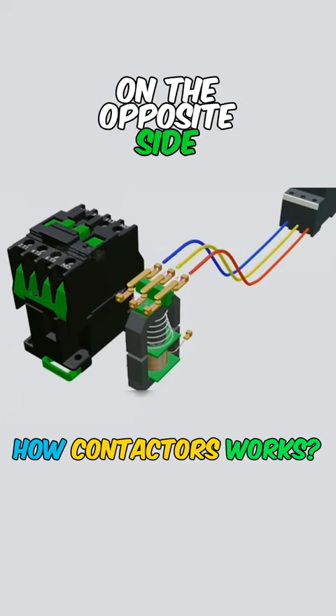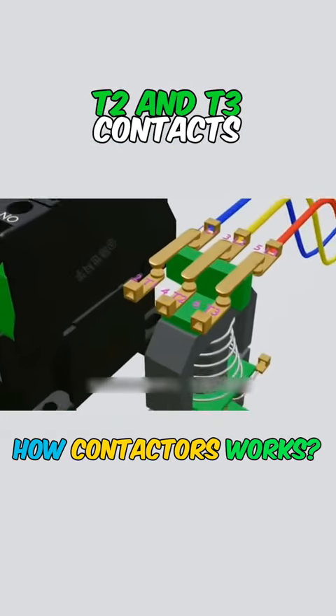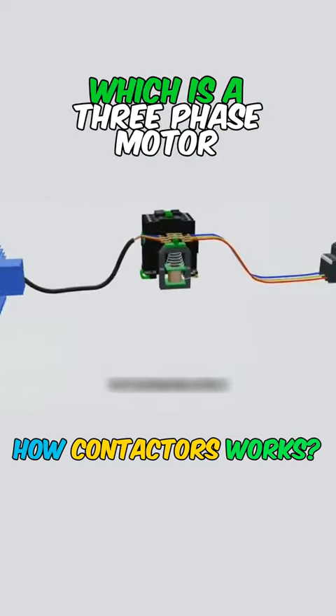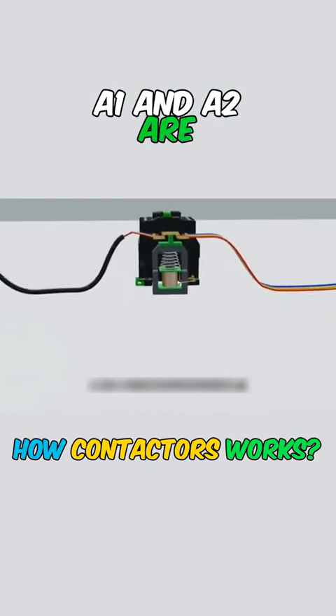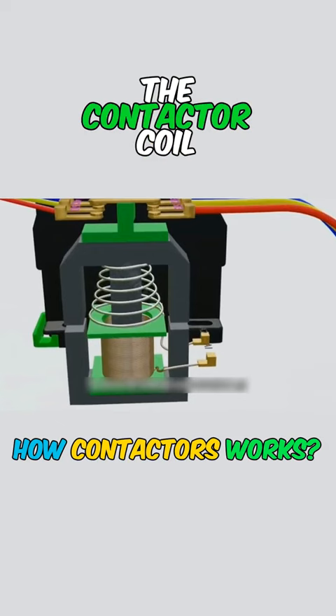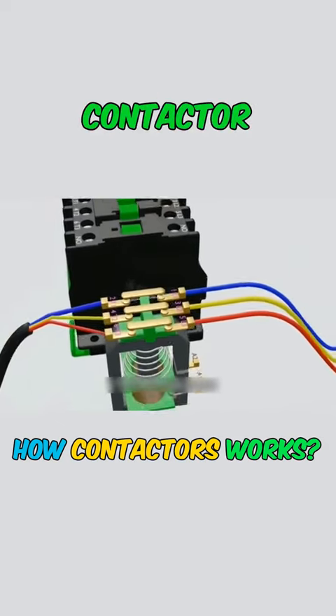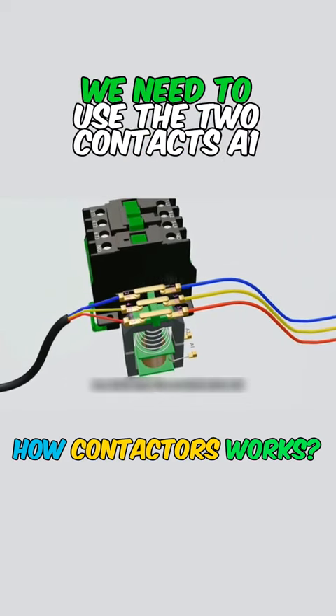On the opposite side, you can see T1, T2, and T3 contacts. They are directly connected to the load device, which is a three-phase motor as shown in the picture. A1 and A2 are the connecting contacts of the contactor coil. They are used to control the contactor, so if we want to engage or disengage the contactor, we need to use the two contacts A1 and A2.